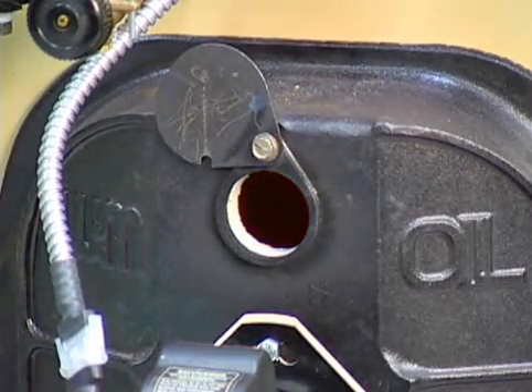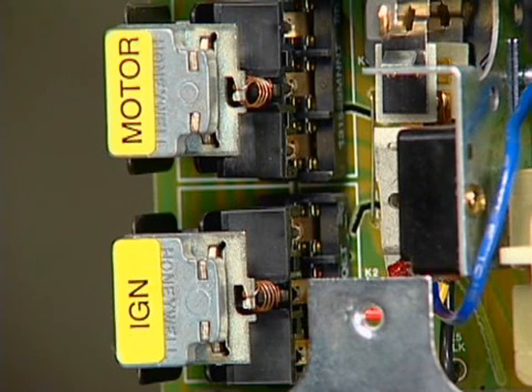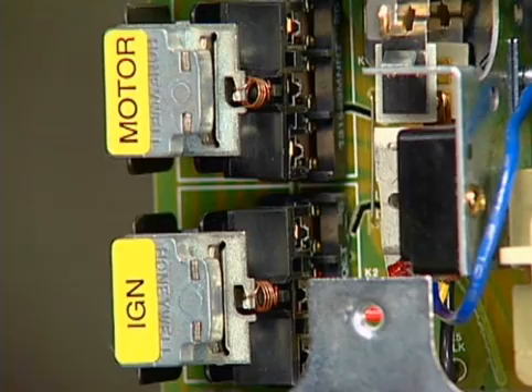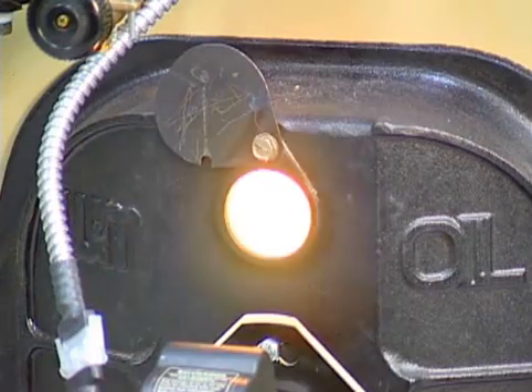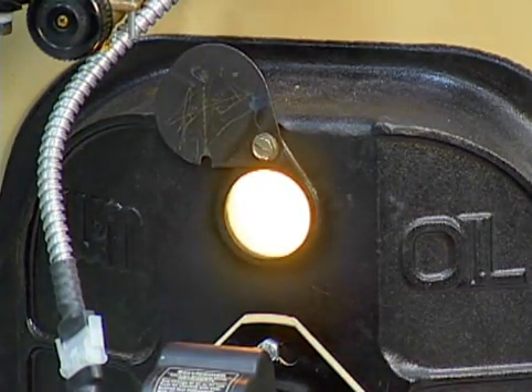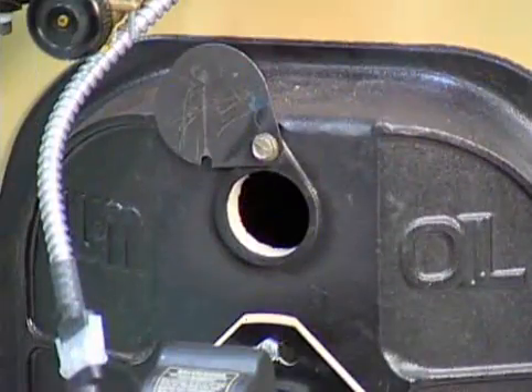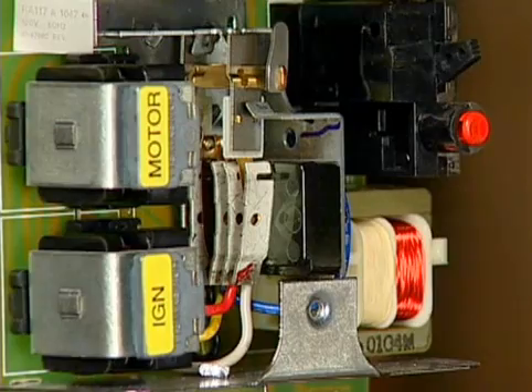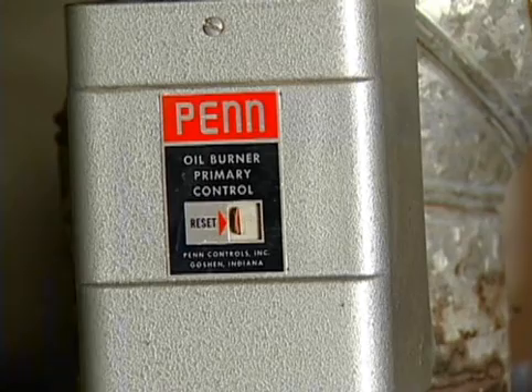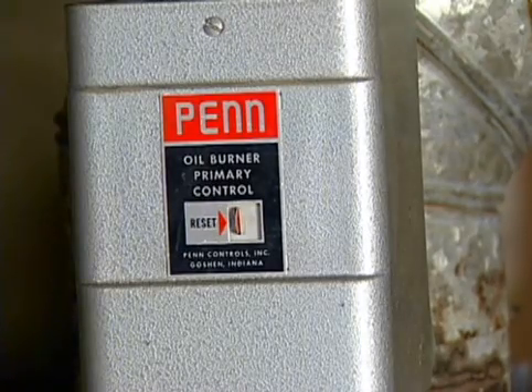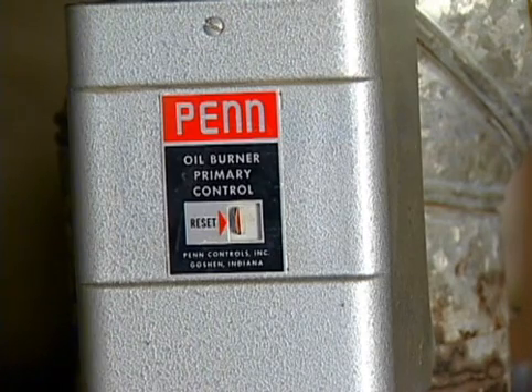If the flame is lost during the run cycle, the RA 117A shuts the system down for approximately 1 minute and makes one attempt to restart. If the flame is re-established, the system will continue to operate normally. If the flame is not re-established, the system shuts off on safety. Some stack-mounted primary controls do not make the attempt to restart. They simply shut off on safety when flame is lost during the run cycle.